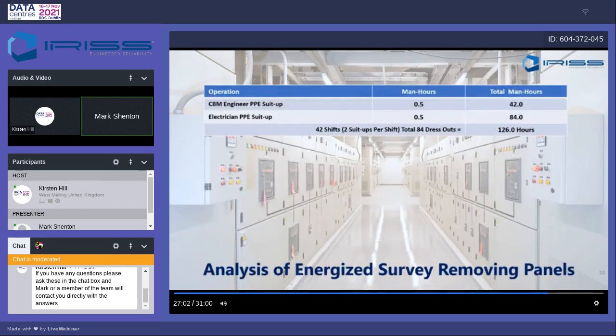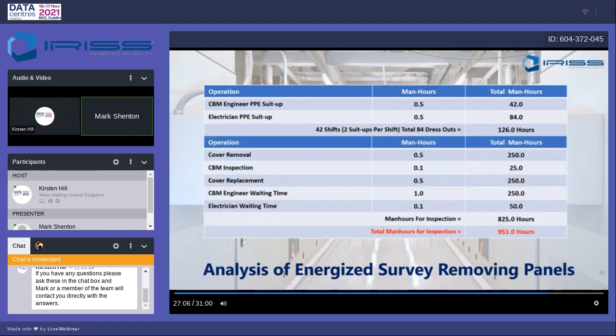PPE suit-up times for the engineers and electricians for panel removal was 126 hours. The man hours for the inspection covered about 250 panels to be opened, half an hour per panel. The CBM inspection itself was 25 hours, or 6 to 10 minutes a panel.